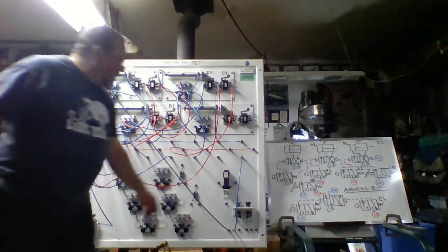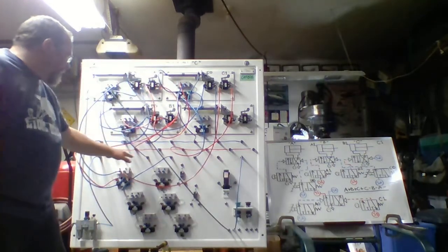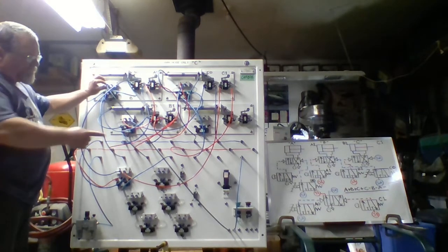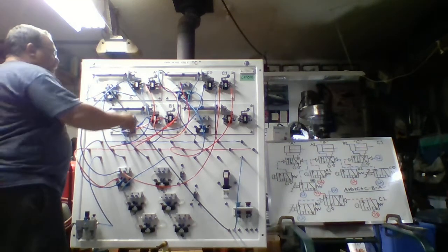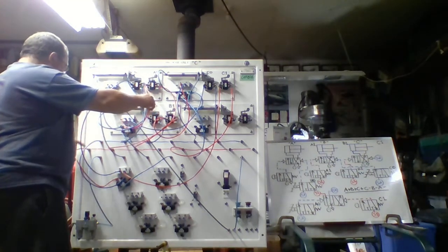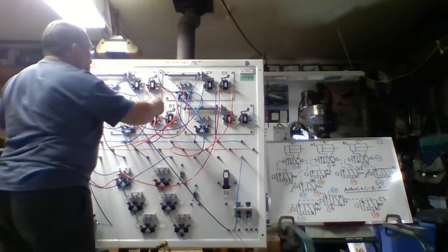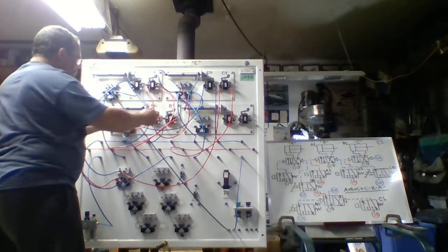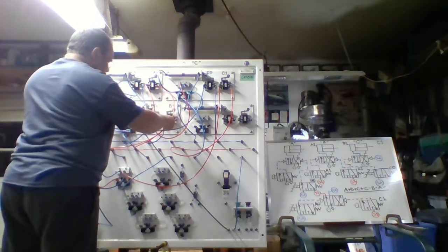Comparing that over here on the board, here's our push button as shown there. This is my main source, this lower portion on the manifold. And you can see I'm piloting for A. When I push the button, of course, A extends. It gets on A1. We look at A1, the red is identifying source 1 right across the manifold. B, of course, is source 2. We look at A1, and right here, as you can see, we're supplied at source 1. We come out, we pilot for B to extend. That in turn gets on B1.